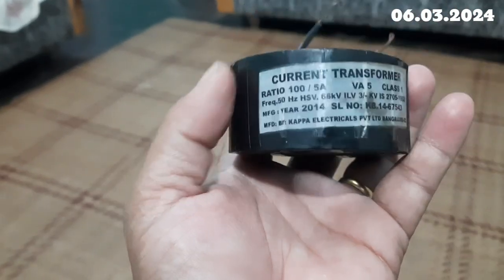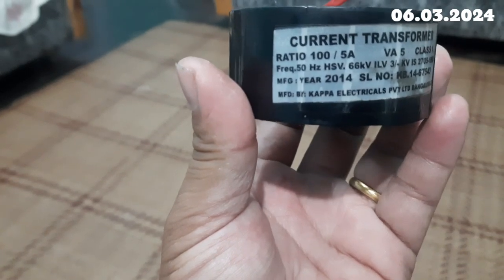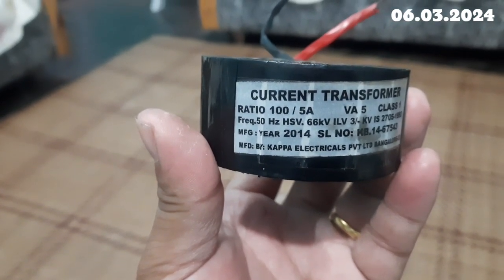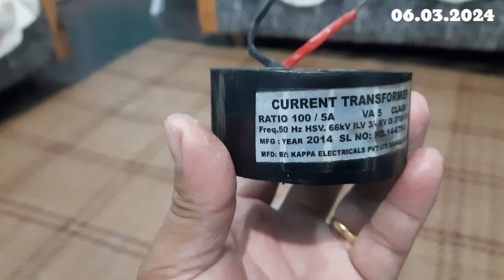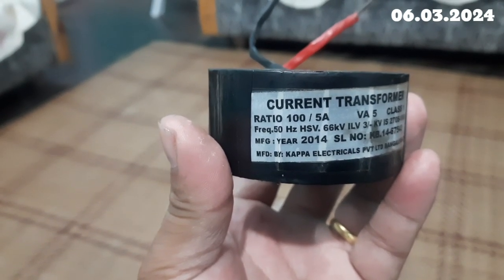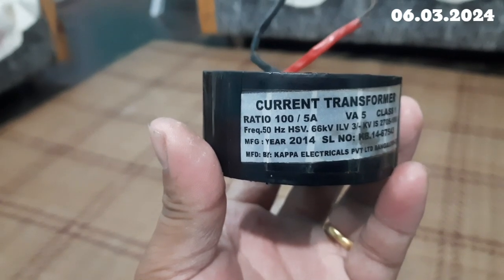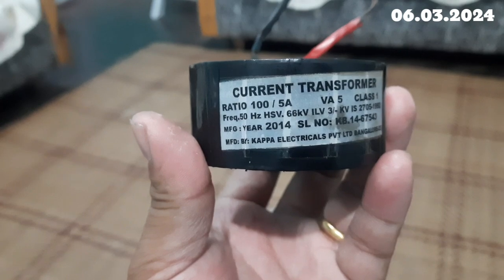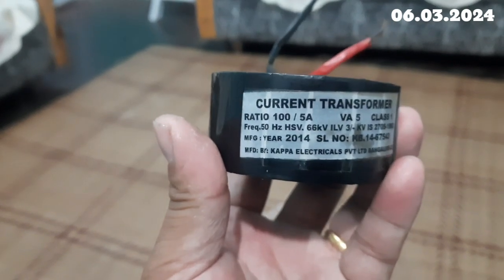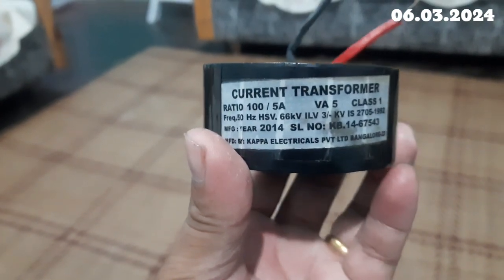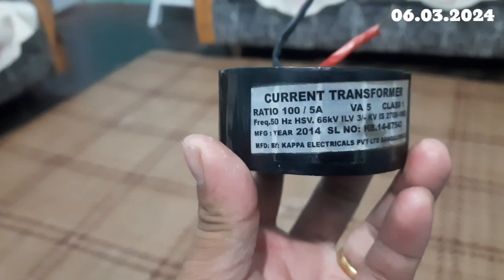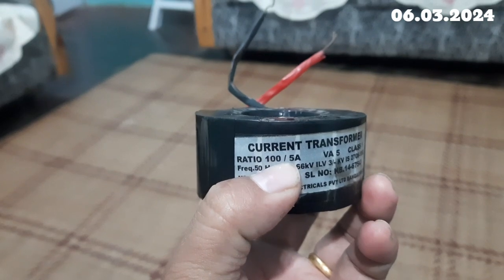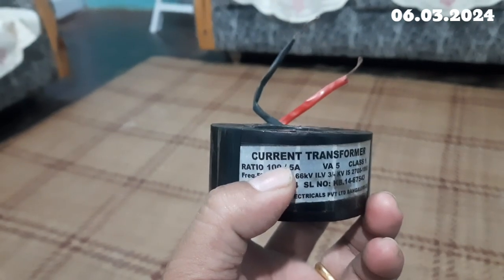All right, so here the only difference from the previous one is the ratio, 100/5. Depending on your connected load or your demand, you can calculate accordingly. Take the demand as P, and then use the formula P = √3 VL IL cos φ. Then accordingly you will get the current. If, for example, your current value using that formula is around 83 or 84, then you can use a CT of current slightly higher, 85 or 86.